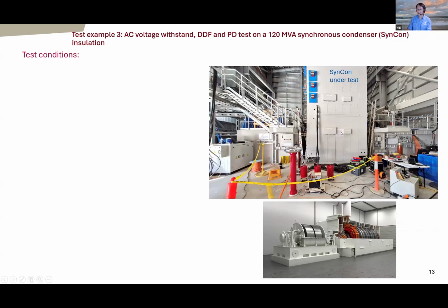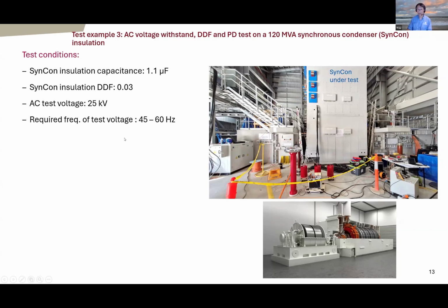But this is a big case, right? It's just a big rotating machine. So it's a gigantic load. This particular one is 1.1 microfarad. But the loss is very low, so the reactive power needed to test is very low, with a test voltage of 25 kV, and the frequency can be varied between two extremes. So the required test power is over 200 kVA, right? Big, but the real power required is only 6.5 kilowatt.